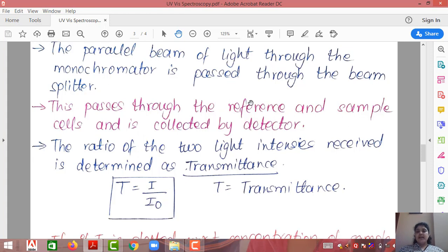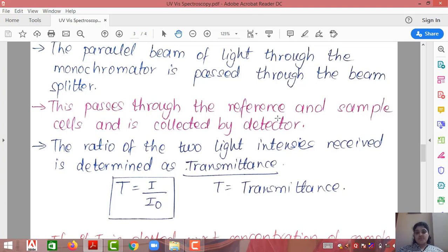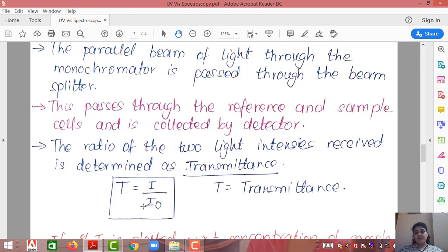When light strikes the reference cell, depending upon the number of atoms per unit volume — that is the density of the sample — the light will be absorbed more or less. If concentration is more, absorption is more and transmittance will decrease. The ratio of the two light intensities received is determined, and that is known as transmittance T, where T = I/I₀. I is the intensity of the sample and I₀ is the intensity of the reference.